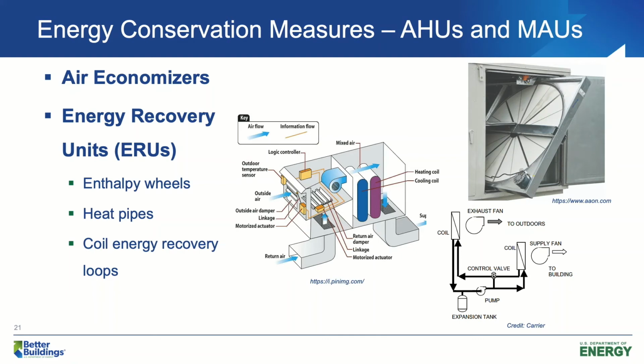Enthalpy wheels are the most energy efficient because they can recover both sensible and latent energy, but they do have drawbacks. They have some risks of air cross contamination. If you have a really high requirement on your air quality, you probably want to avoid enthalpy wheels. For that application, you can consider heat pipes ERUs. Heat pipes ERUs are not as efficient as enthalpy wheels because they can only recover sensible heat, but they have almost no risk of air cross contamination. The third option is coil energy recovery loops. This technology is very useful when your intake air ductwork is pretty far away from your exhaust air ductwork, but you do need to build a new loop, buy a pump and some fluid to transfer the heat around.